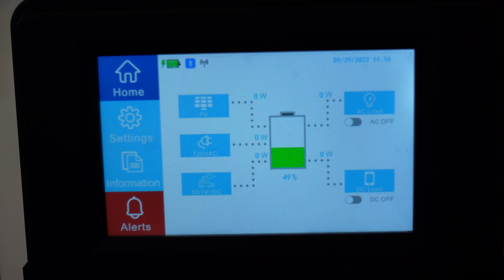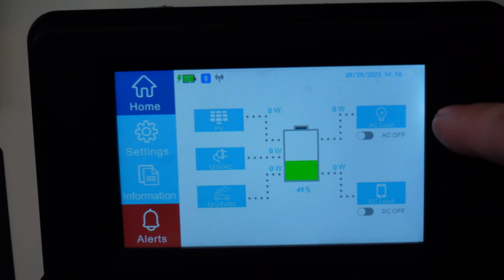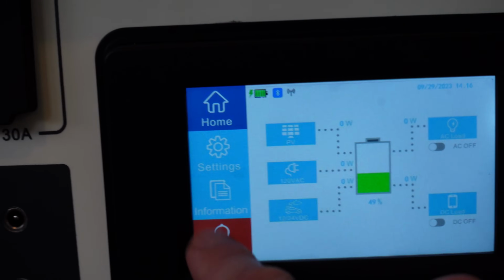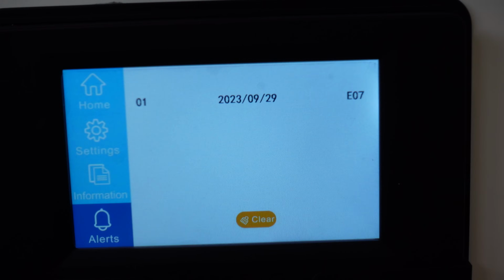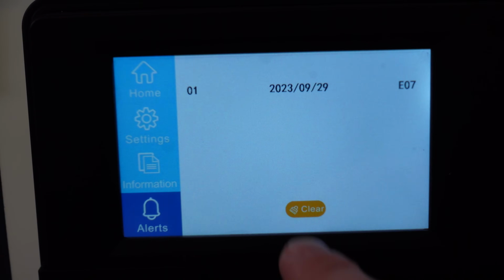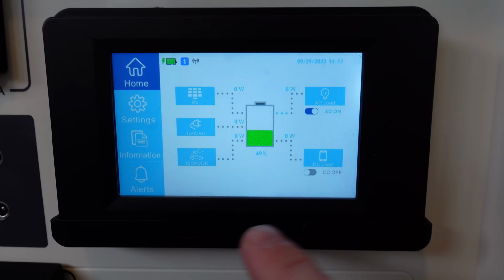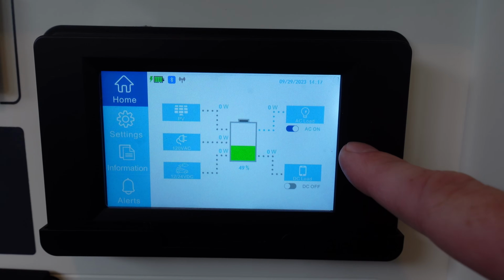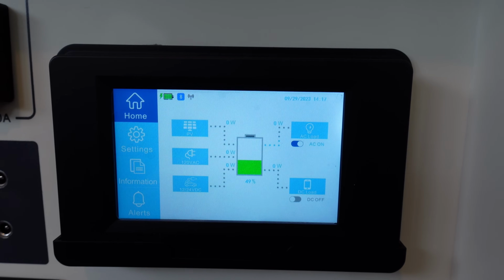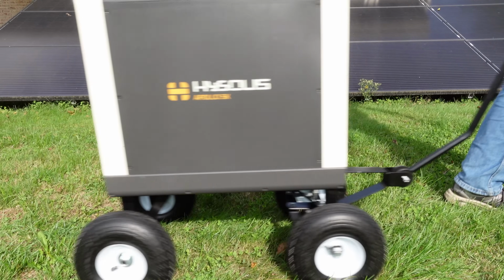All right, now I really made it mad. I had it up to approximately 4,000 watts and it did actually shut down. And you can see here we have error code E07. So now I'm satisfied that the overload protection does indeed work. And after we've cleared the fault, you can see we're able to start the inverter back up again. So we're all good there.